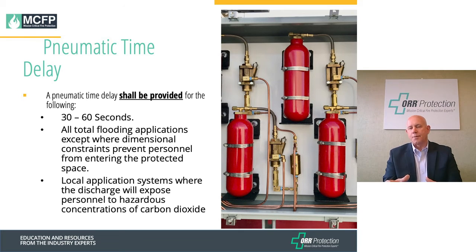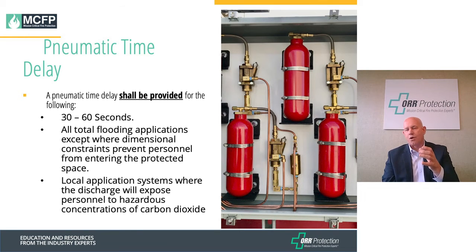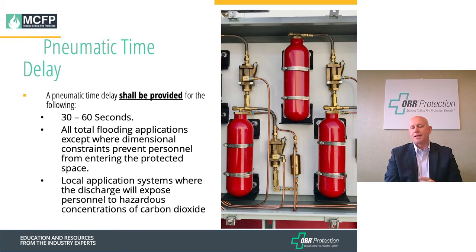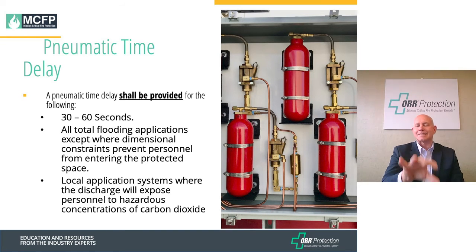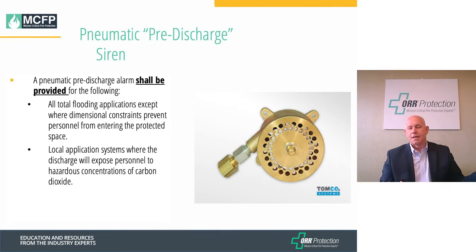Pneumatic time delay bottles — also called accumulator bottles — work by accumulating CO2 until it builds enough back pressure to fire the piston on the main discharge line. The delay can be 30 or 60 seconds, depending on the duration set. These are a new feature for many systems that currently lack them, and they shall be provided per code. Pre-discharge pneumatic sirens are also a 'shall' — as heard in the discharge video, the siren comes up loud after the electronic audible.